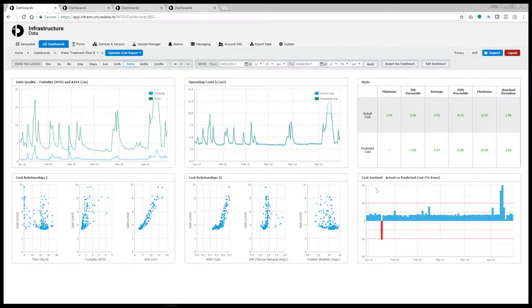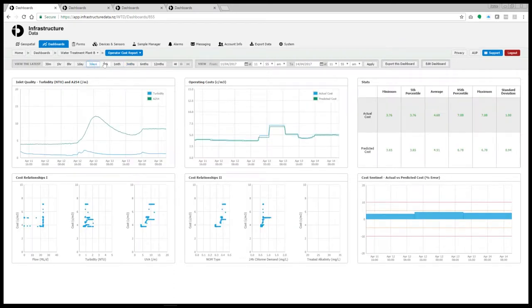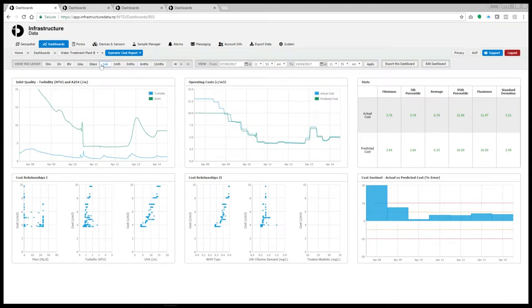With the predicted cost, we can also run a cost sentinel feature. This is a comparison of the actual cost versus the predicted cost, and we can alert based on errors. If there's a deviation, the suggestion is that it's an off-normal situation — put simply, there's something going wrong on the plant that warrants investigation. We're looking at a period of three months here, but we can also quickly change the time periods and zoom in to look at three days or a week, and assess the effect of these variables over time on operational cost.